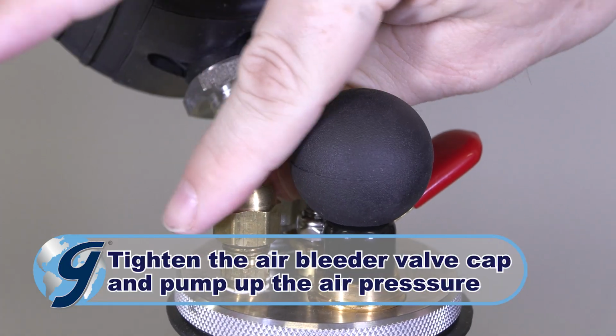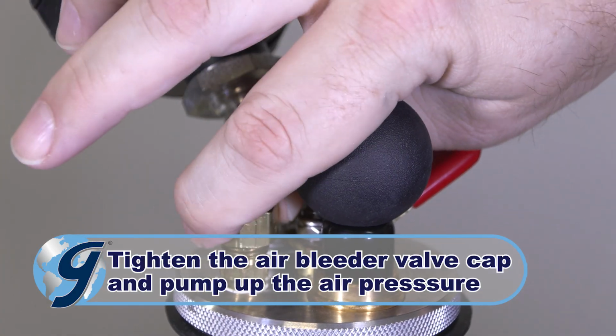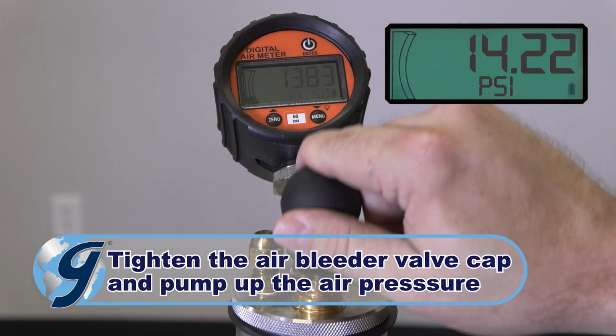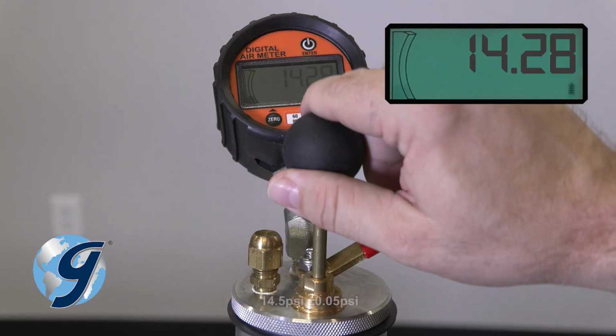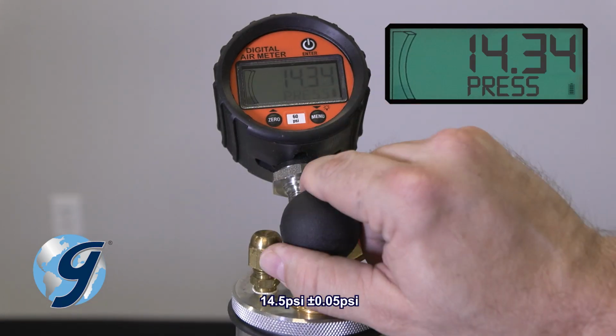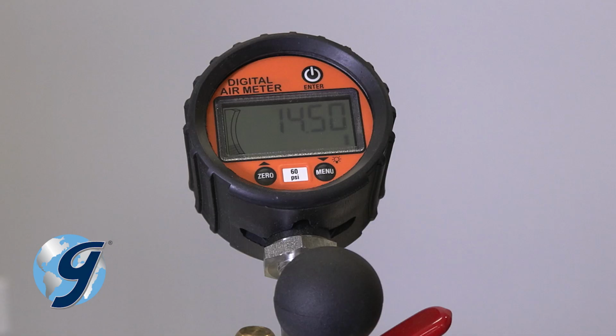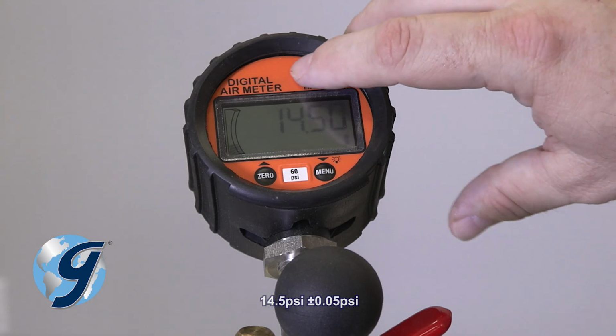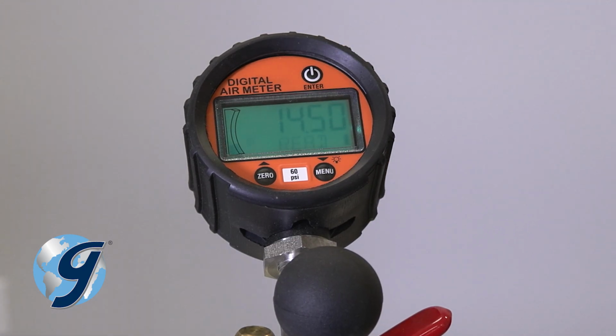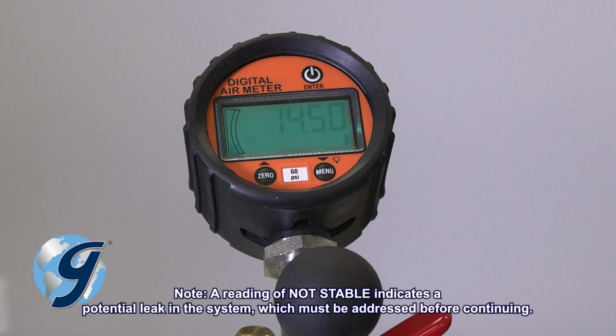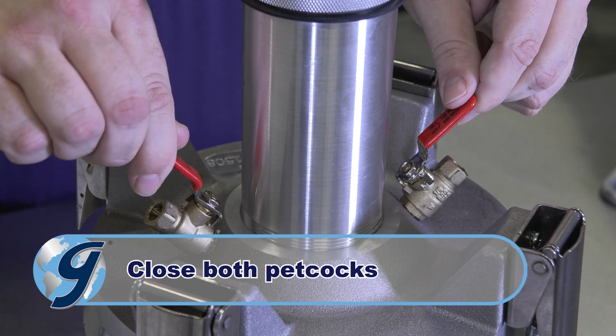Now, tighten the air bleeder valve cap and pump up the air pressure to 14.5. Allow the gauge to stabilize and then press Enter. If the gauge displays low or high, make appropriate adjustments and then press Enter. Now close both petcocks.